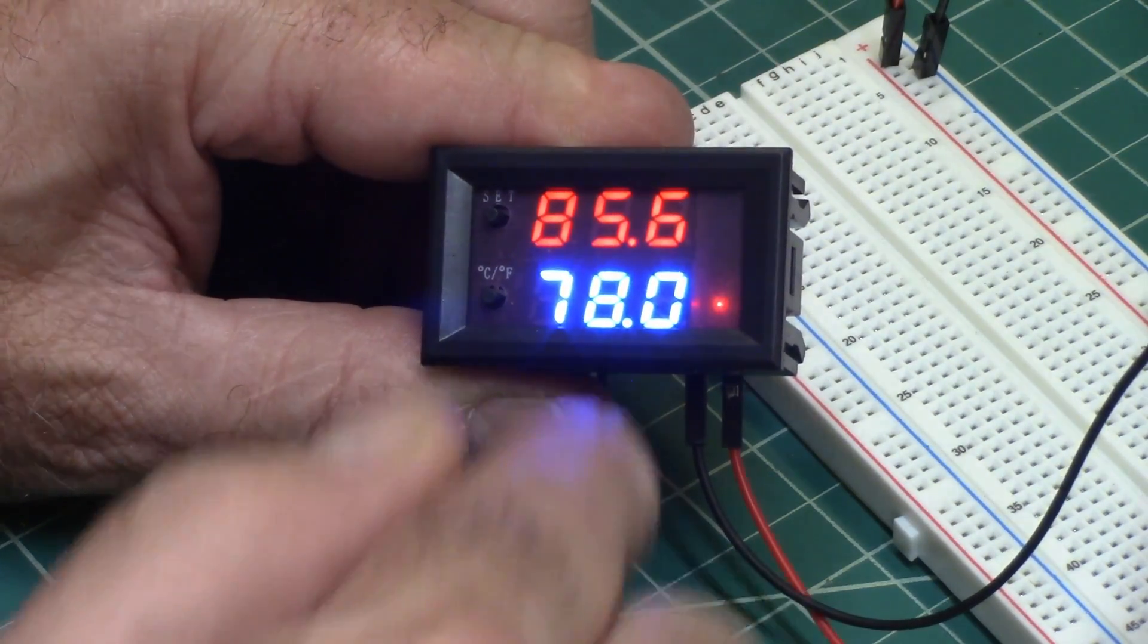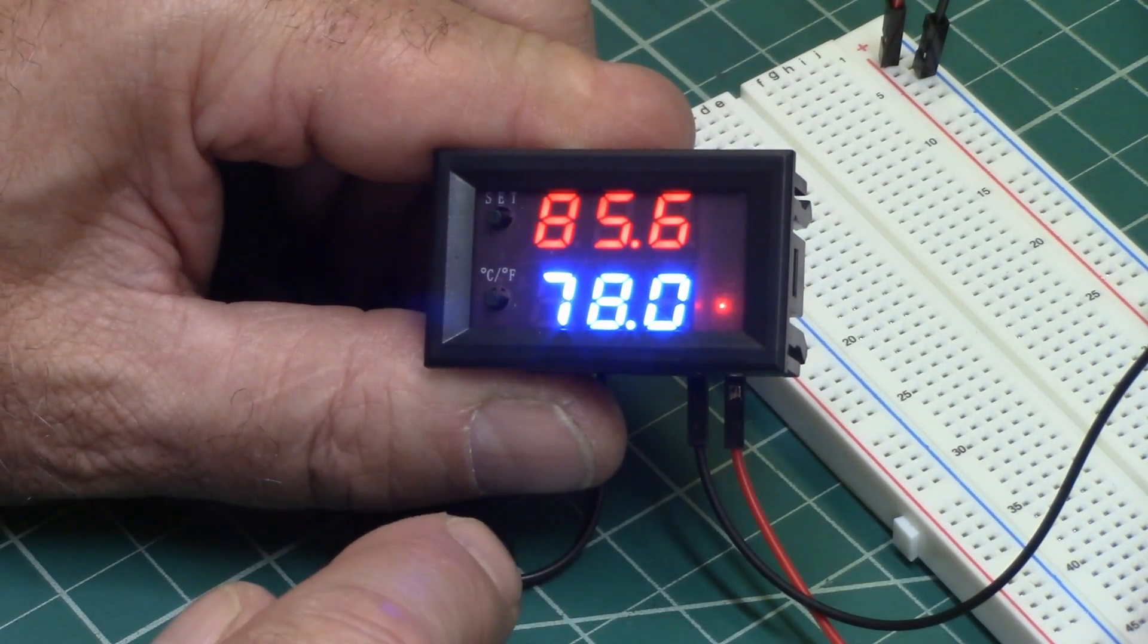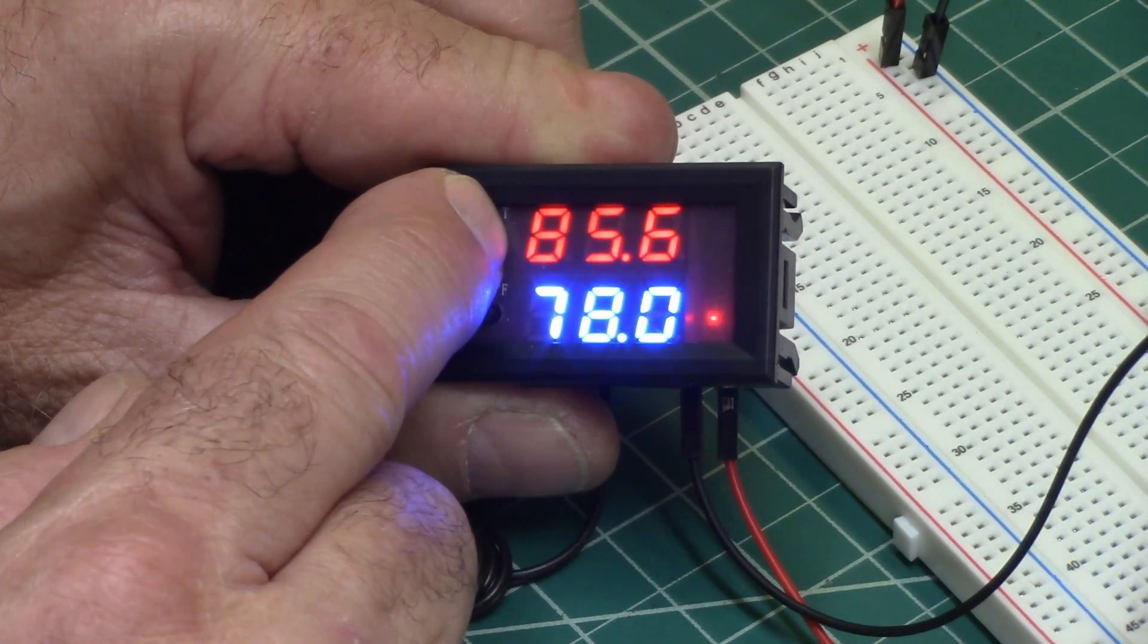Because you don't want something that's going to bring it down to 78, and then when it hits 78.1, it's going to come on, and then at 78 it's going to go off. And it'll be cycling back and forth really fast, and wear your equipment out. So you want to have like a degree or two, at least, difference.